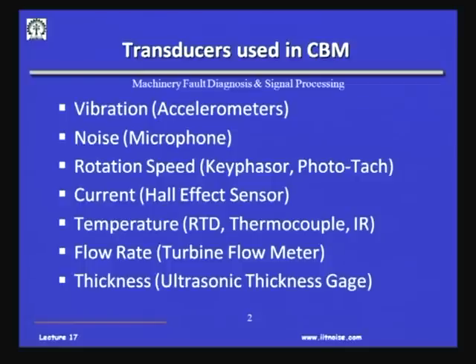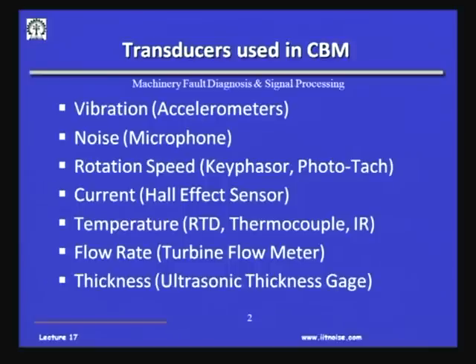Another very important NDT - non-destructive test - technique is the measurement of thickness. As I was telling you, because of fluid flowing through a pipeline, deposits get deposited on the inner wall. That is going to affect the flow rates. Such scale formation will reduce the internal thickness of the pipe. From the outside, how do I know that such a buildup has occurred? This can be very easily measured online by an ultrasonic thickness gauge.